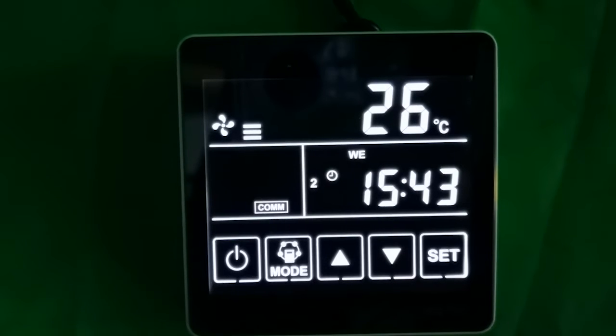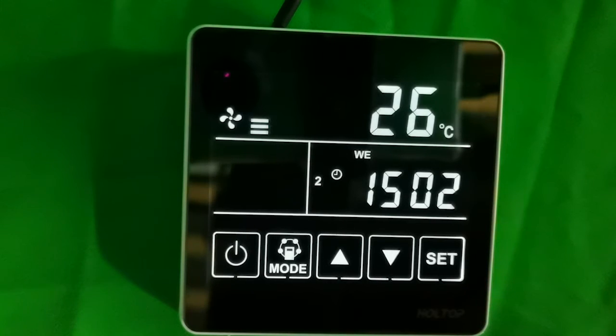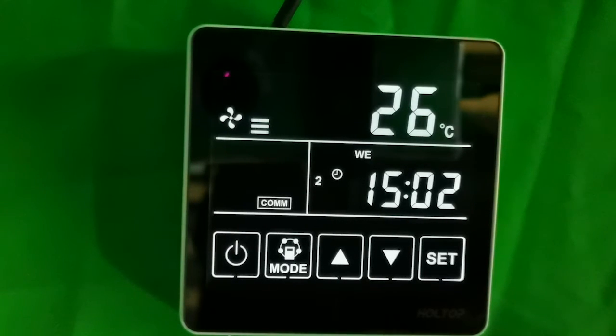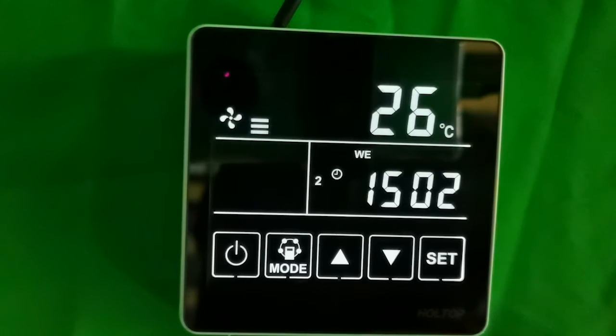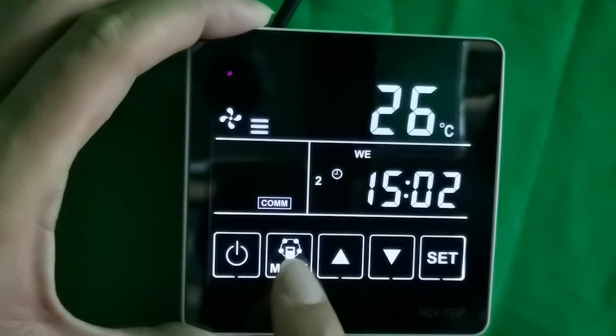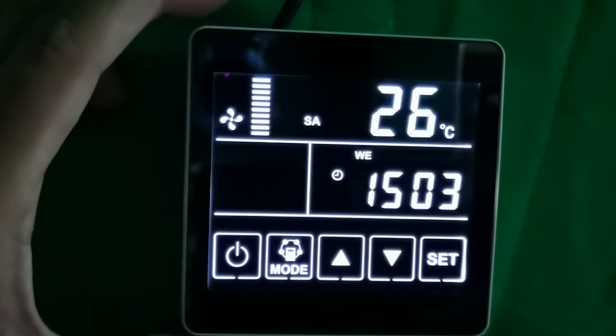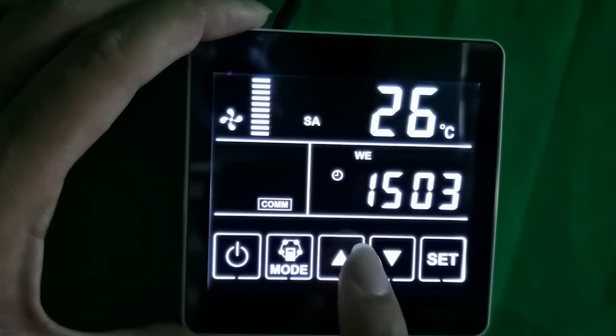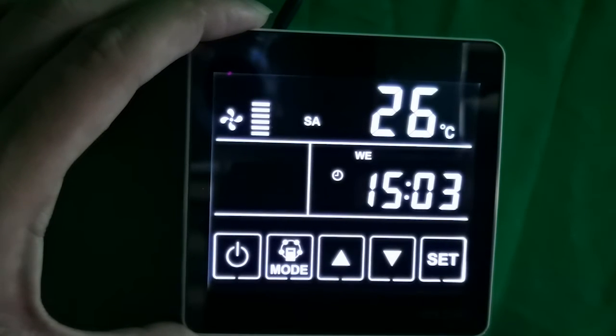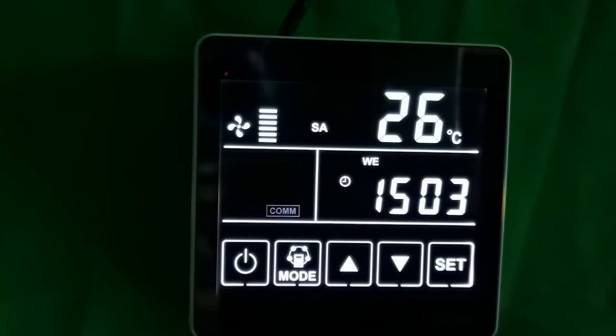Next, let's show the fan speed setting. We can set the fan speed in manual mode and automatic mode. For example, the fan speed setting in manual mode: under the supply air or exhaust air interface, press mode, then under supply air, press the up and down arrow key. The speed of the exhaust air or supply air can be set in the same way.